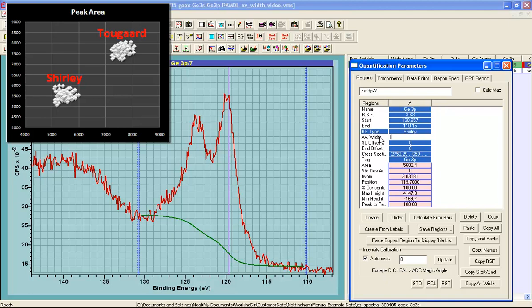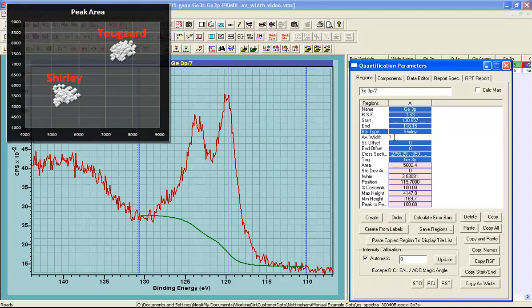The average width parameter is different in the sense that this influences the precision with which we measure the area of a peak. So once we have selected a background type and we have made an informed decision about how we wish to calculate the peak area, then the area that we calculate is influenced by the average width in terms of precision of measuring that area.